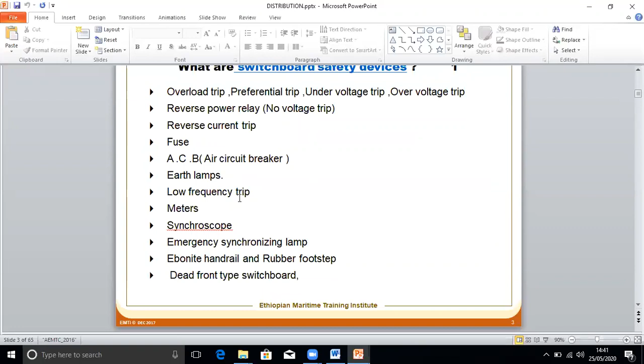Switchboard survey performed during the dry docking. Check the voltmeter, ammeter, wattmeter, calibrations and accuracies. Check all the trips: overcurrent, reverse power, preferential trip. Synchronizing test. Switchgear in each terminal to be checked for insulation resistance, minimum 1 megohm. Tightness of loose joint connections, bus bar supports, fuse holders. AVR and ACBs. Earth detection lamps and the insulation monitors. So these are the basic switchboard survey parts.